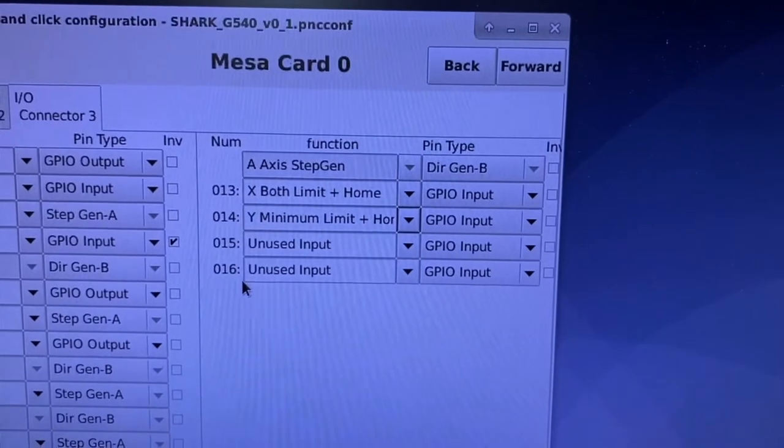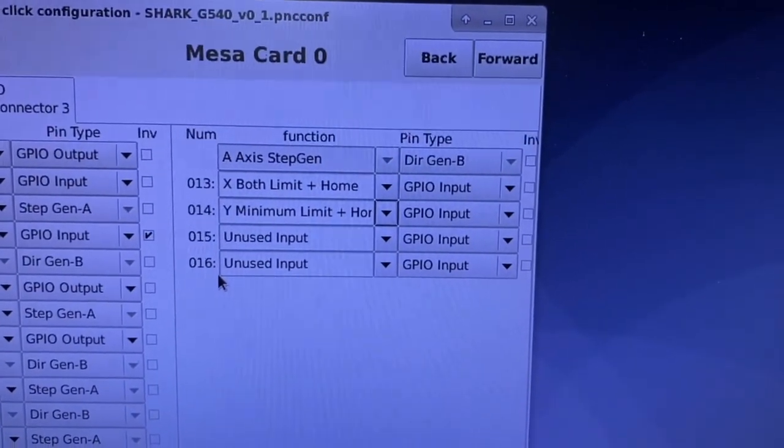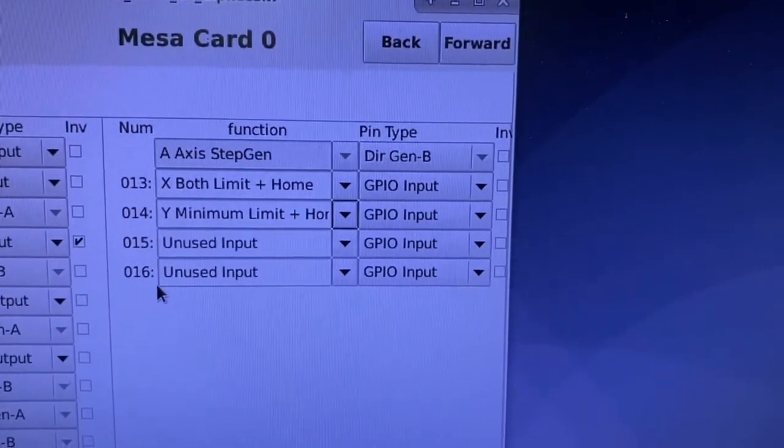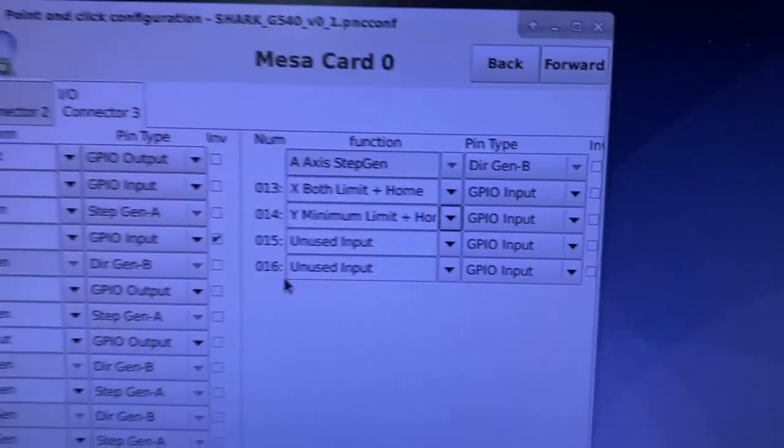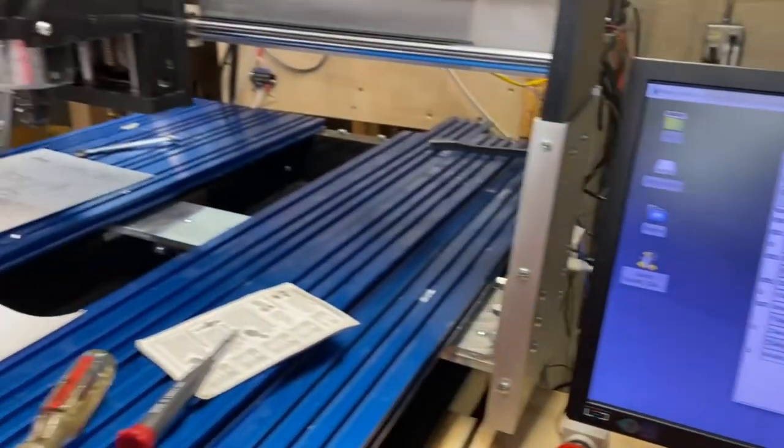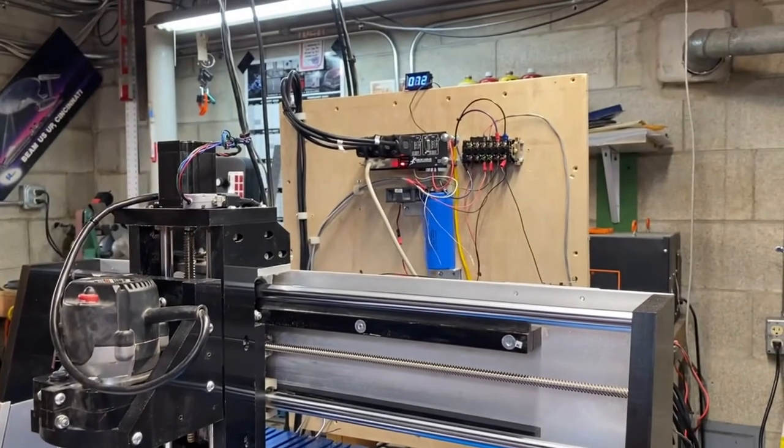This sensor is going to be the y-axis minimum plus the homing switch. So I make that selection and that sensor is configured. Now you may ask why didn't we put two sensors in series, two switches in series, like we did with the x-axis. The circuitry in these inductive limit switches is sophisticated enough that I actually prefer just to put them on two separate inputs. So we're going to use a separate input for the y-axis maximum switch.